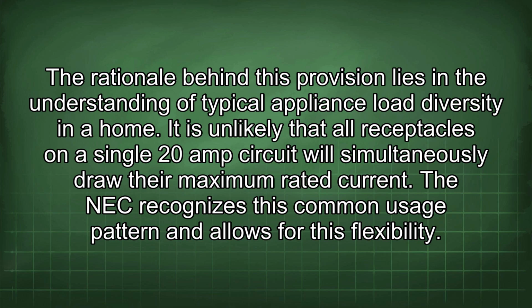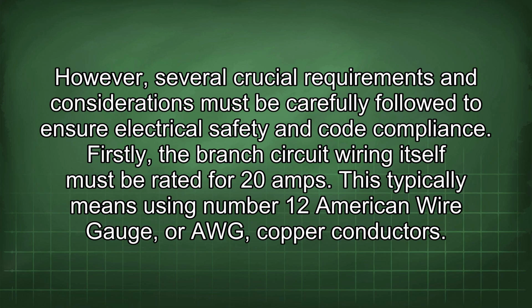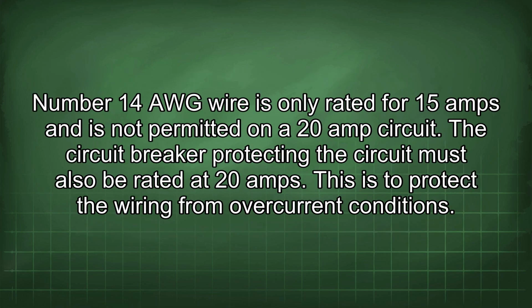It is unlikely that all receptacles on a single 20-amp circuit will simultaneously draw their maximum rated current. The NEC recognizes this common usage pattern and allows for this flexibility. However, several crucial requirements and considerations must be carefully followed to ensure electrical safety and code compliance. Firstly, the branch circuit wiring itself must be rated for 20 amps. This typically means using number 12 American Wire Gauge, or AWG, copper conductors. Number 14 AWG wire is only rated for 15 amps and is not permitted on a 20 amp circuit.